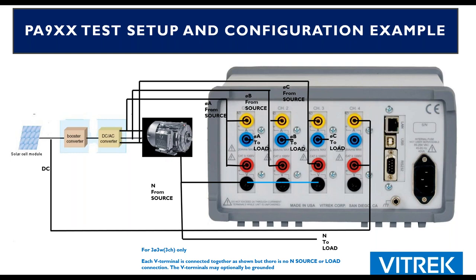So now I go turn around to the front panel and do my efficiency calculations. I'm going to take my measurement results from VPA number 1, which was my channel 4, which is my DC. I'm going to put that in my denominator. And then I'm going to take my VPA number 2, which is my 3-phase voltage and current from channels 1, 2, and 3, and put that on top of my equation. Now I've got my VPA number 2 divided by my VPA number 1, and there's my efficiency.